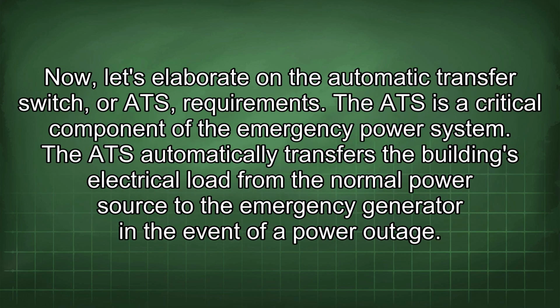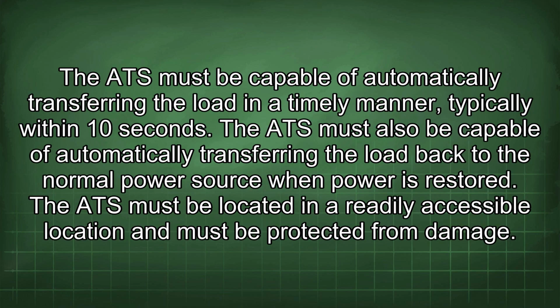Now let's elaborate on the automatic transfer switch, or ATS requirements. The ATS is a critical component of the emergency power system. The ATS automatically transfers the building's electrical load from the normal power source to the emergency generator in the event of a power outage. The ATS must be capable of automatically transferring the load in a timely manner, typically within 10 seconds.